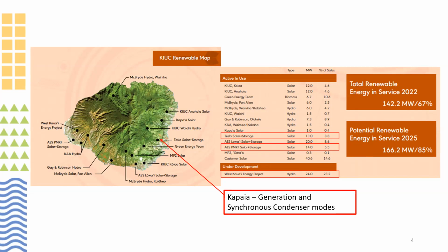Kapaia, when we are running 100%, we do run that in synchronous condenser mode. We have had issues with it - it's been a learning curve for all of us. When we're running 100%, that's running for short circuit stability, and we really don't know what inertia we need, but the more spin we got, we think the better.